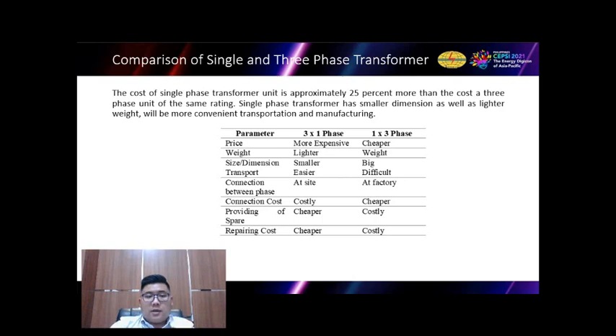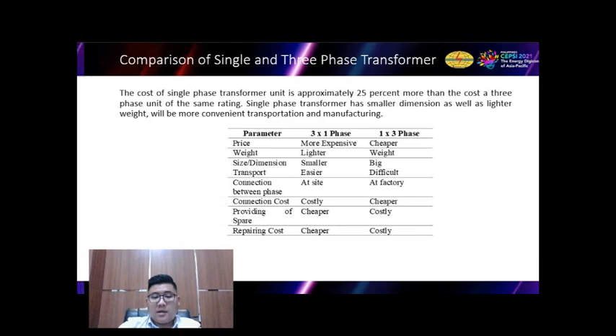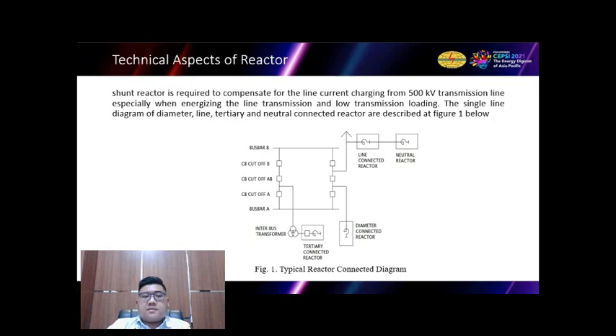In this slide, we are talking about the comparison of single and three-phase transformer. The cost of a single-phase transformer unit is approximately 20% more than the cost of a three-phase unit of the same rating. Single-phase transformer has smaller dimension as well as lighter weight, and will be more convenient for transportation and manufacturing. At this slide, we can see the parameters and the comparison between 3 times 1 phase and 1 times 3 phase transformer. The comparison consists of price, weight, size or dimension, transportation, connection between phase, connection costs, providing of spare, and repairing costs. Now, we continue to the technical aspect of reactor.